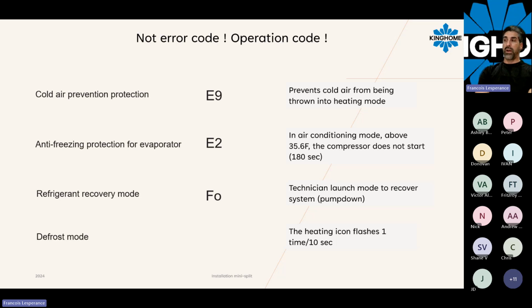When the heating process needs to start, we need to reach at least 56 degrees Celsius at the indoor coil before the system will throw some warm air across the room. So during that time, maybe you will see an E9 operation code on the head. E2 is antifreeze protection of the evaporator.